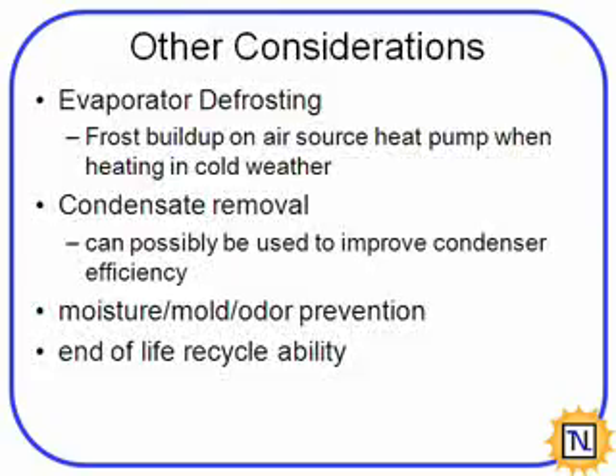Some additional considerations that we have with the system: we took a look at some of the data that showed the defrostings that occurred. So frost buildup will be a problem on the system, and it's something we're working on, the defrost strategy and sensing that and when to end that cycle. So it's an important consideration. Condensate removal is another one. Can we do anything, an added benefit with this? We spray it on the condenser. Can we improve its performance? Is it worth doing that?